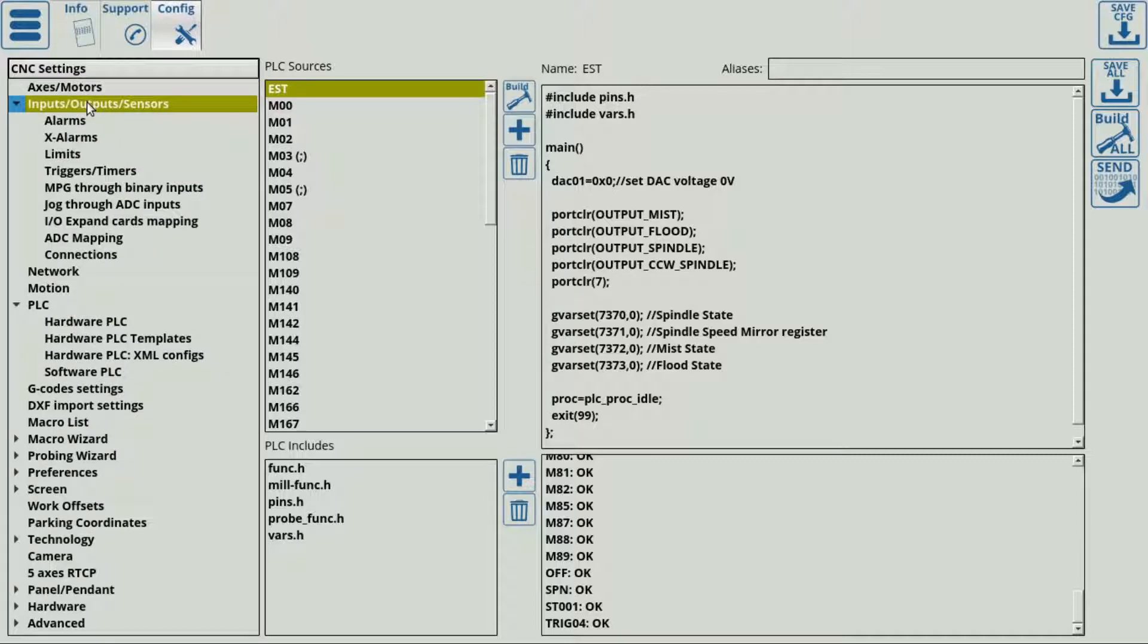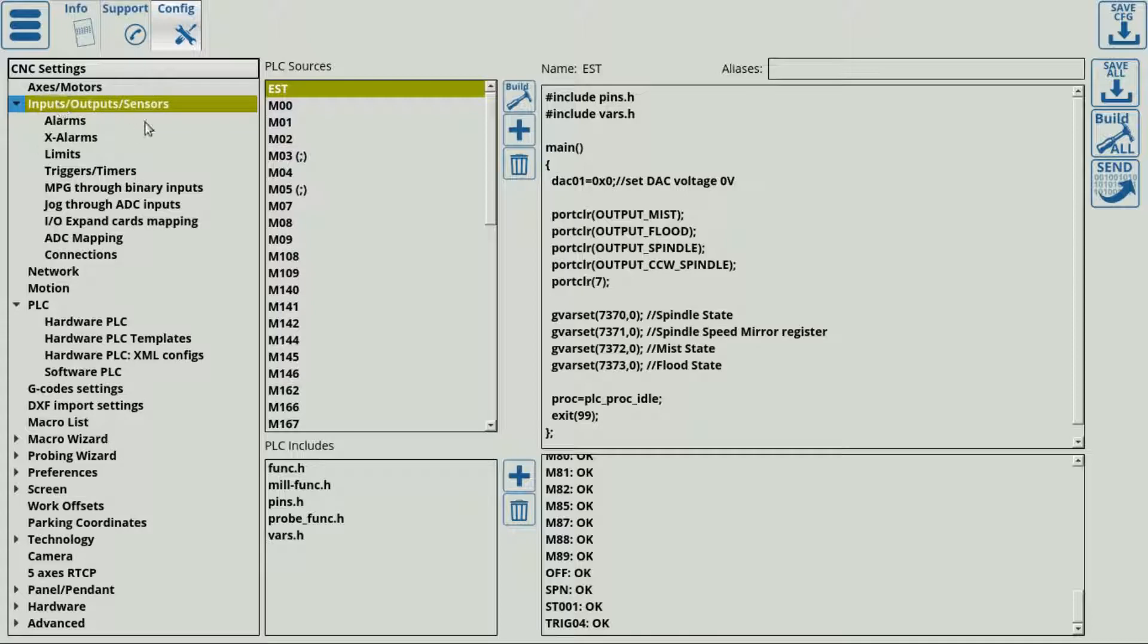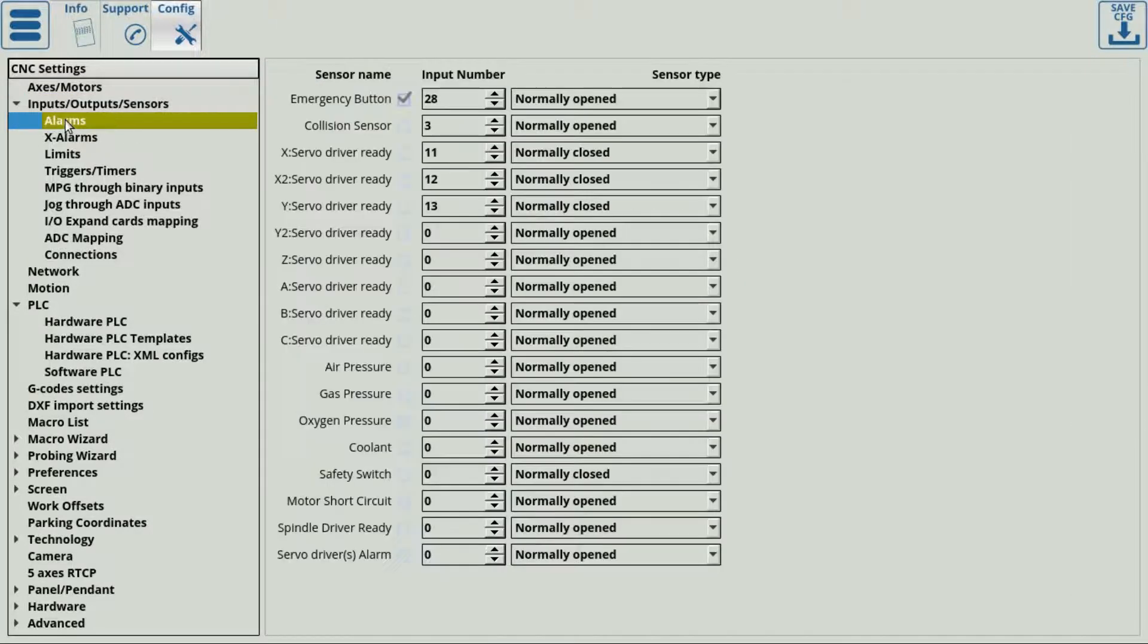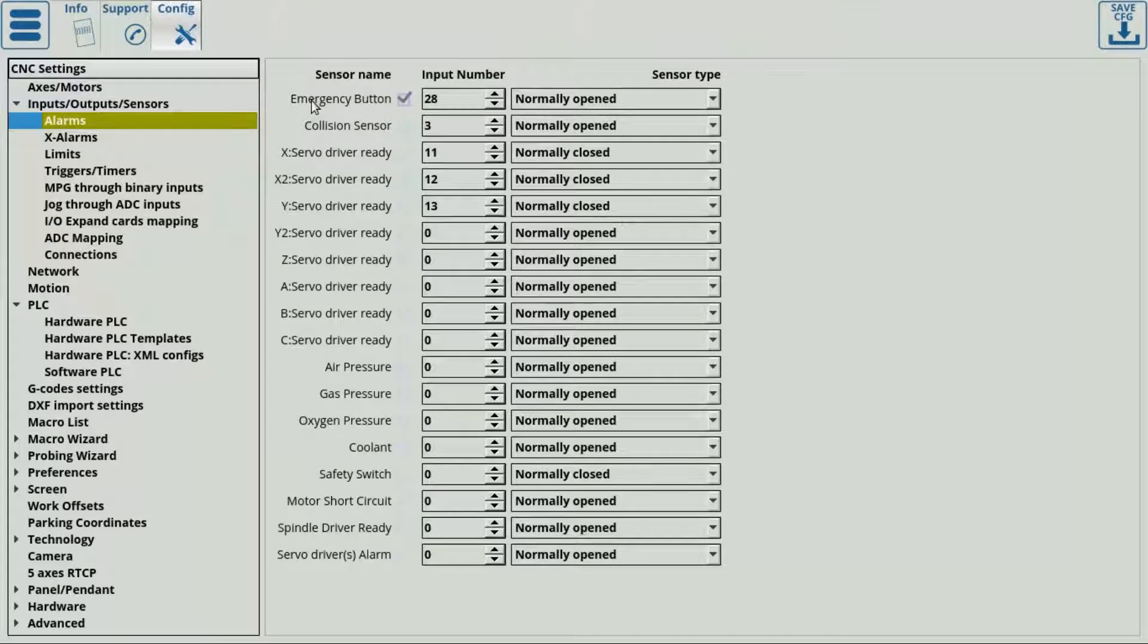Then you can set up the actual input for the emergency alarm. That can be done by going into the inputs output sensors tab within the same settings and going into alarms. Here I already have my emergency button tied to input number 28, which is assigned to be normally opened.